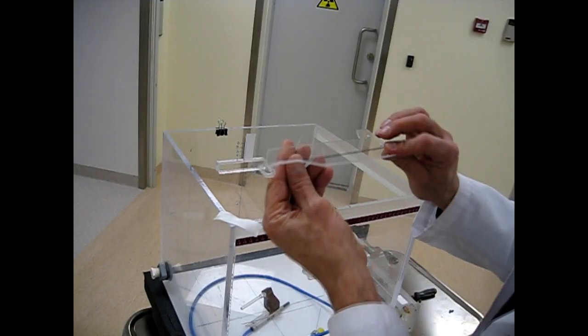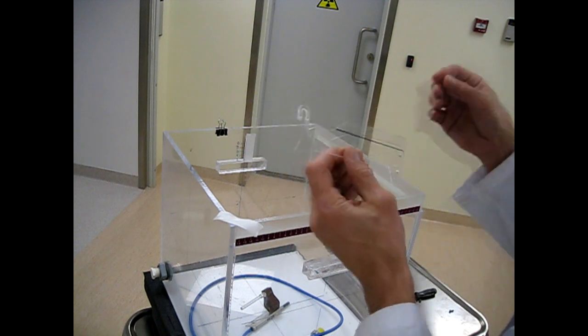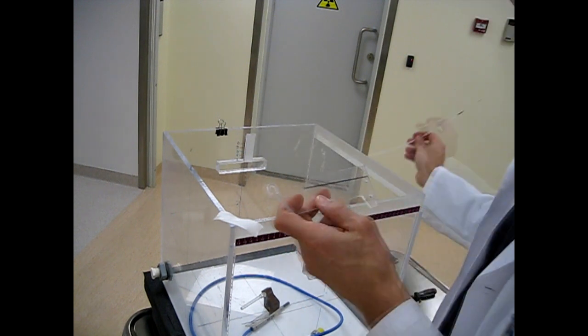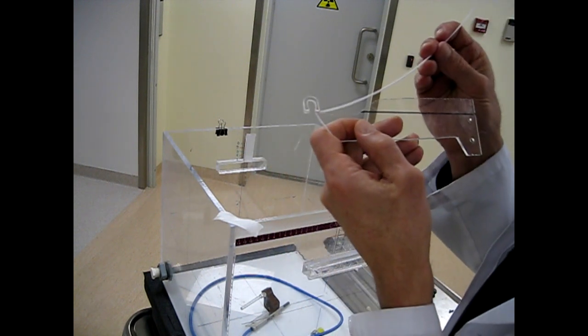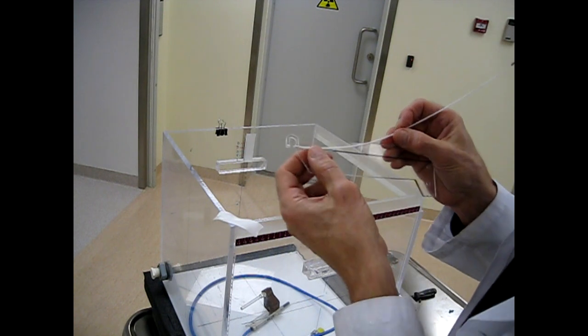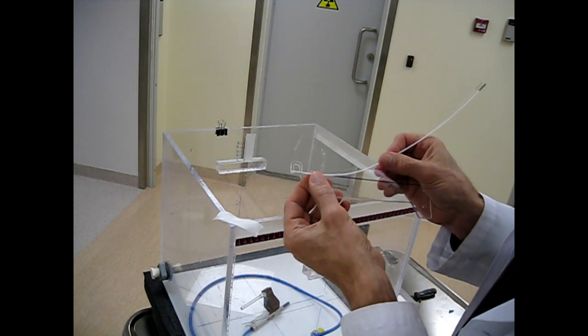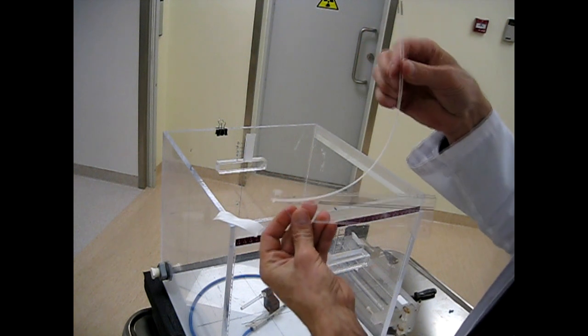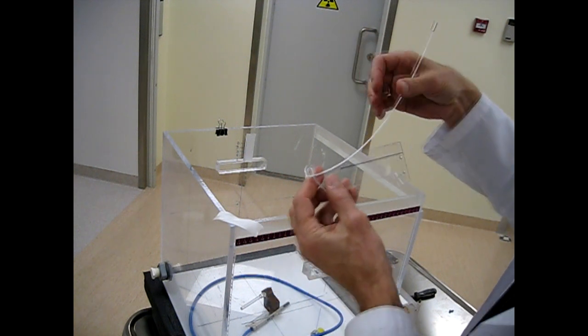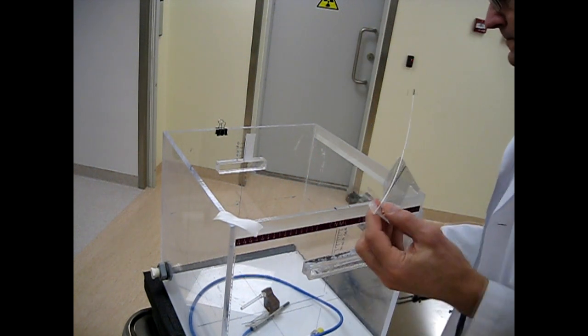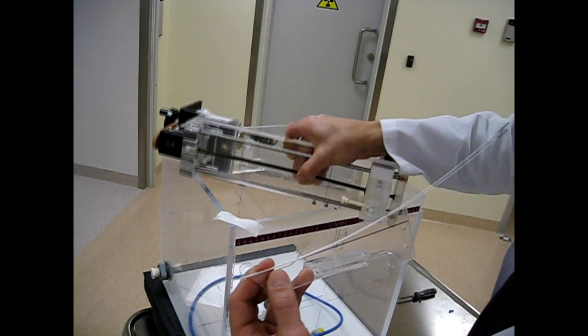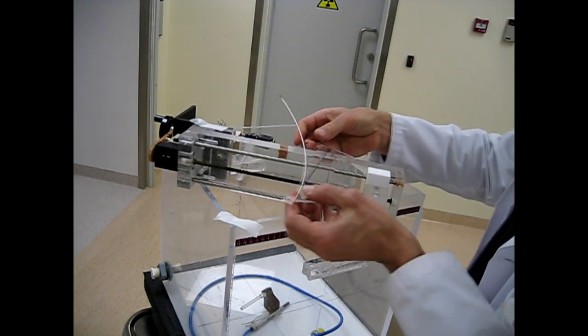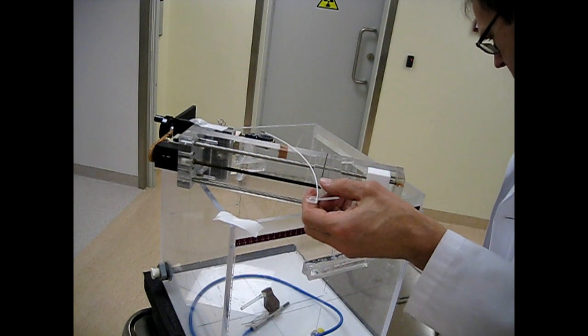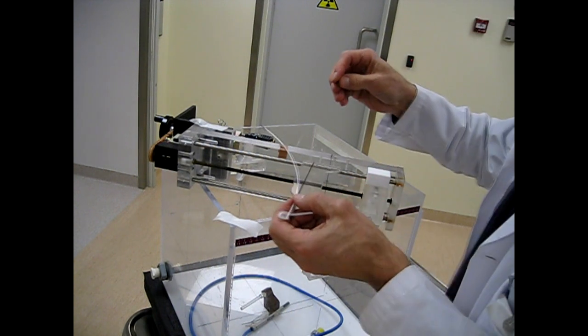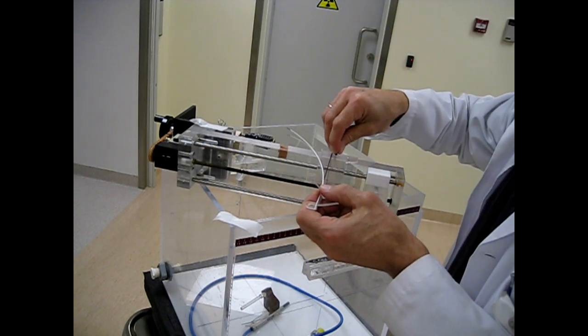Now about the holder of the mold probe. It has a new arc-type design to minimize the amount of non-aqueous material around the radiation source, and as you see, the source catheter is curved in order to make an effect of pressing down the end part of the cable with the source, to be sure that the radiation source is now in direct contact with the lower wall of the catheter.